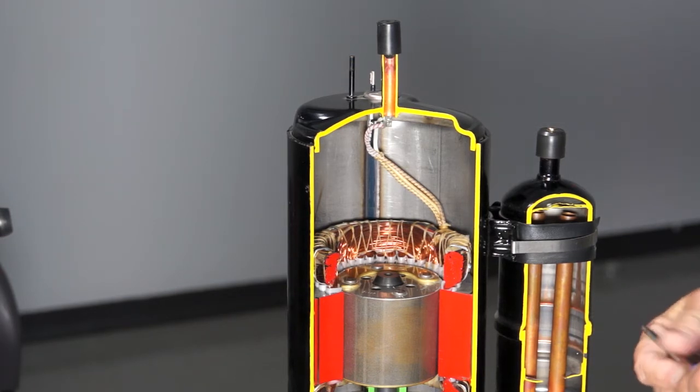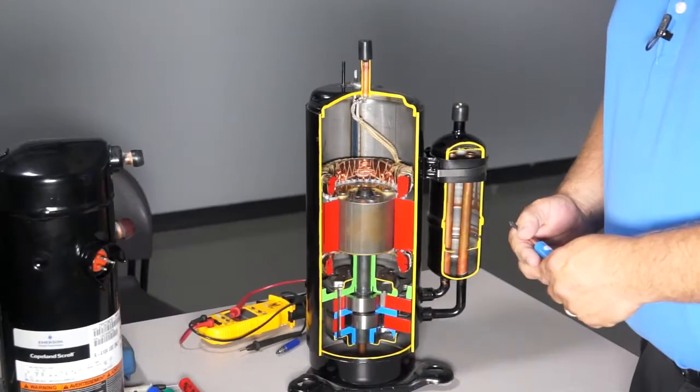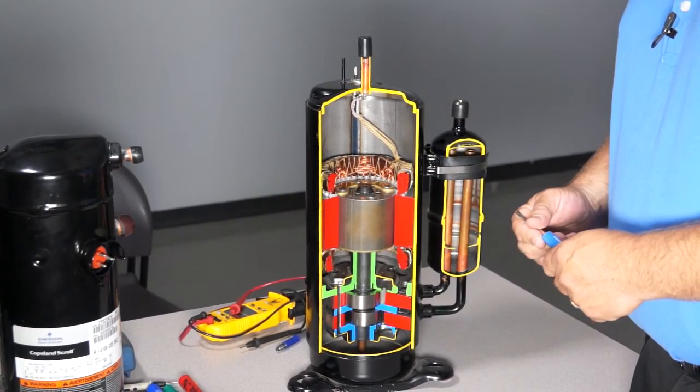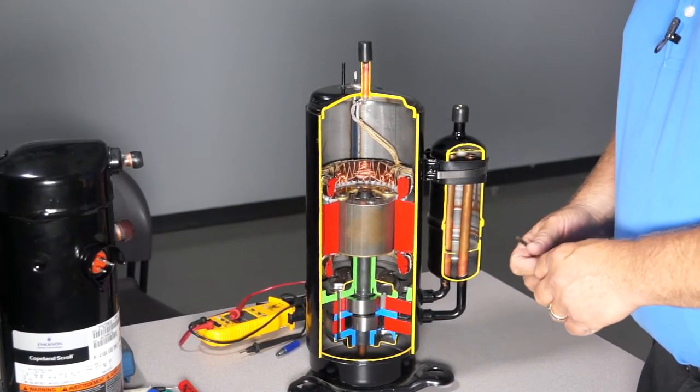If you're tripping the circuit breaker, you probably have either a grounded or shorted compressor winding. If it's tripping the overload, then it's possible that the compressor is physically locked up and the motor just can't turn.